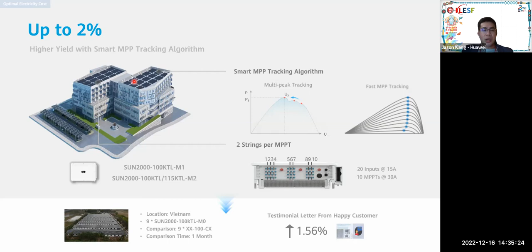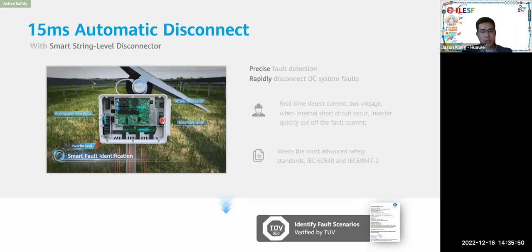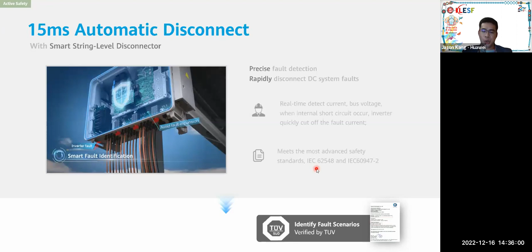On top of that, we also have a smart string level disconnector, the red colored one at the bottom. It's not an isolator, it's more like an MCB, whereby it can trip on its own. This tripping protects from PV faults as well as internal faults within the inverter itself. It complies with IEC standards, IEC 62548 and also IEC 60947-2.